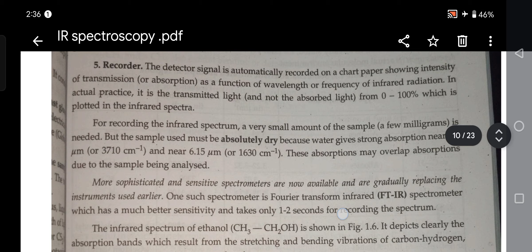In actual practice, it is transmitted light from 0 to 100%, which is plotted in the infrared spectrum. For recording the infrared spectrum, a very small amount of sample is needed, but the sample used must be absolutely dry because water gives strong absorption near 2.7 μm and near 6.15 μm. These absorptions may overlap absorptions due to the sample being analyzed.